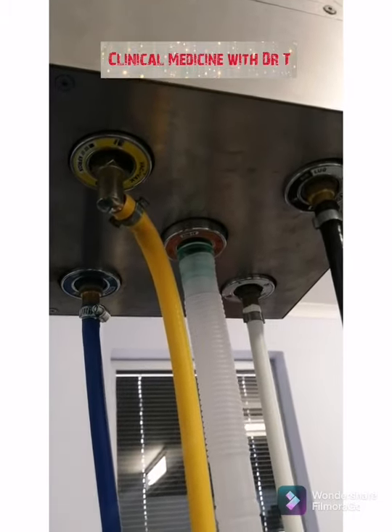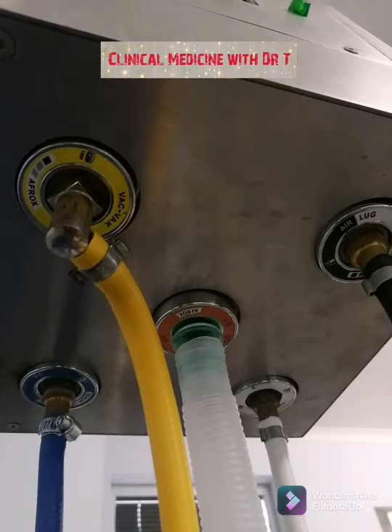That's very important. And also, if you pay attention, for each and every gas, the metallic thing at the end where you tuck in the pipe has a different shape. There is no way you can put oxygen into, for instance, a different socket. Not sure what to call it, maybe an inlet. So you cannot mix them up. It just won't fit.